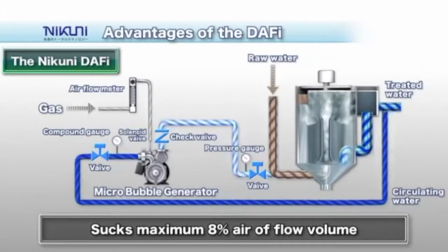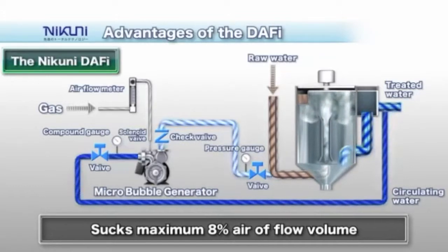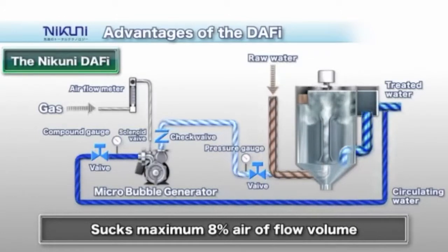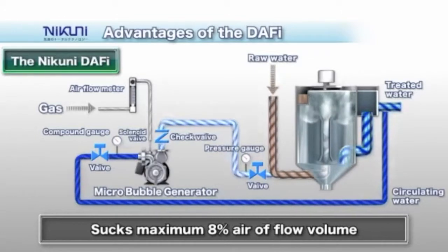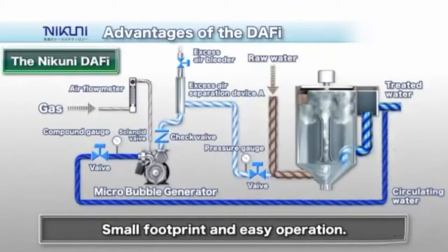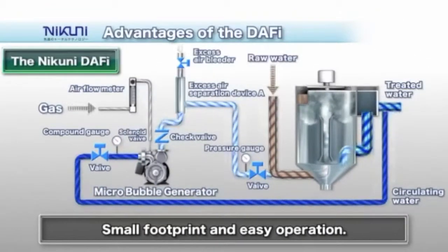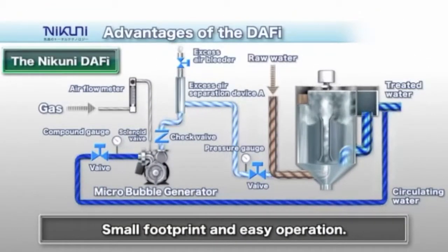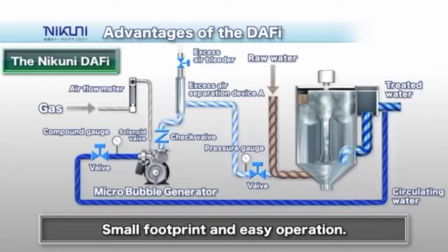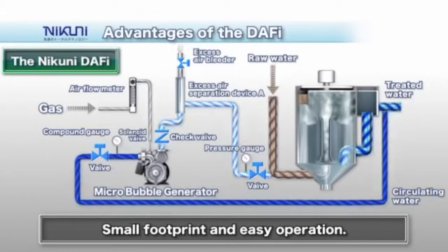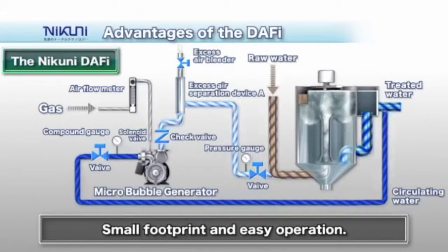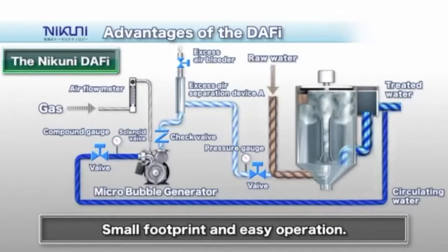To operate the micro bubble generator, first adjust the valve on the discharge side of the pump to the required pressure, then lightly close the valve on the suction side of the pump creating a negative pressure state. Finally, open the valve of the air flow meter to allow the prescribed amount of air to flow in.